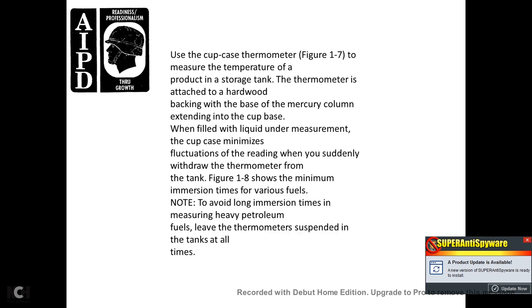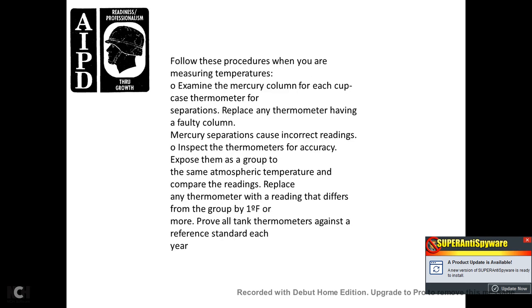Use the cup case thermometer to measure the temperature of the product in a storage tank. The thermometer is attached to a hardwood backing, with the base of the mercury column extended within the cup base. When filled with liquid, the cup case minimizes fluctuation of the reading when the thermometer is suddenly withdrawn from the tank. Figure 1-8 shows the minimum immersion times for various fuels. To avoid long immersion times when measuring heavy petroleum fuels, leave the thermometer suspended in the tank at all times. Whenever measuring temperature, examine the mercury column for separation in the cup case. Replace any thermometer with a faulty or separated column, as mercury separations cause incorrect readings.